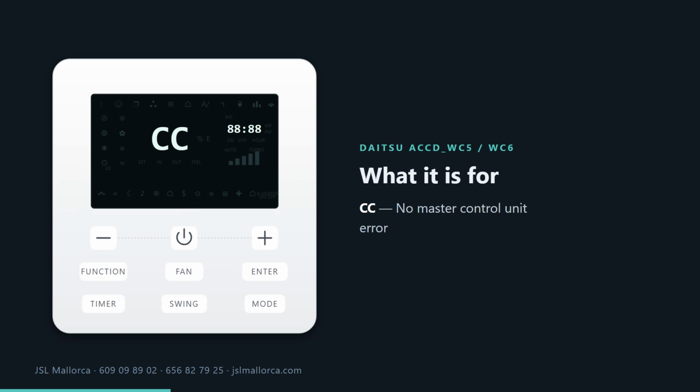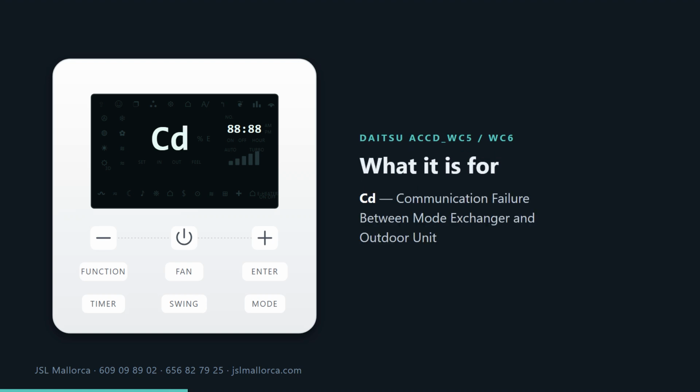Code CC. According to the manufacturer, no master control unit error. Code CD. According to the manufacturer, communication failure between mode exchanger and outdoor unit. Code CE. According to the manufacturer, communication failure between mode exchanger and indoor unit.